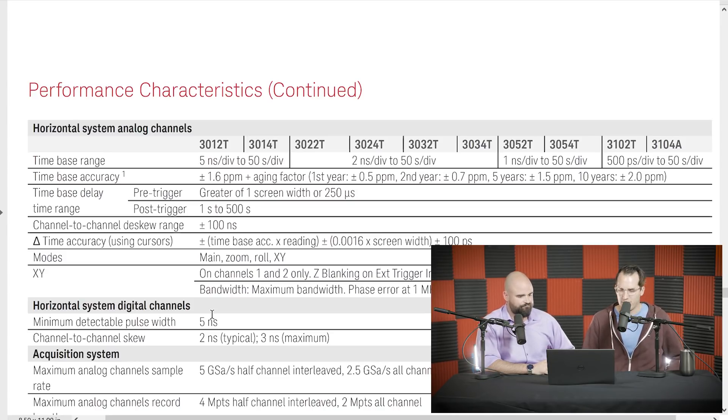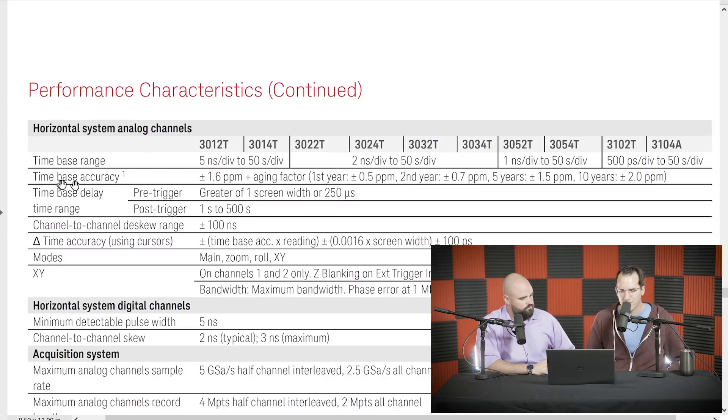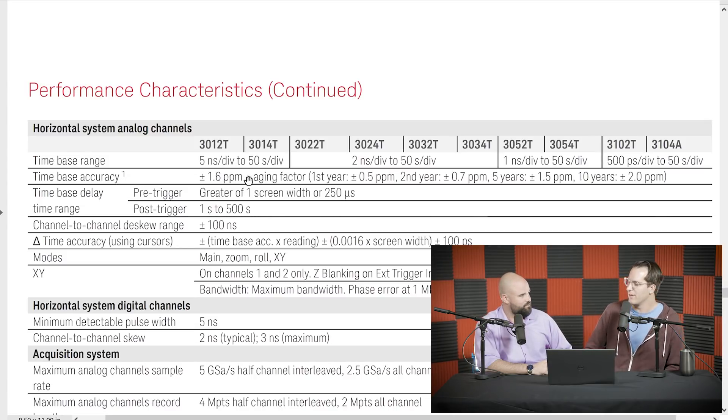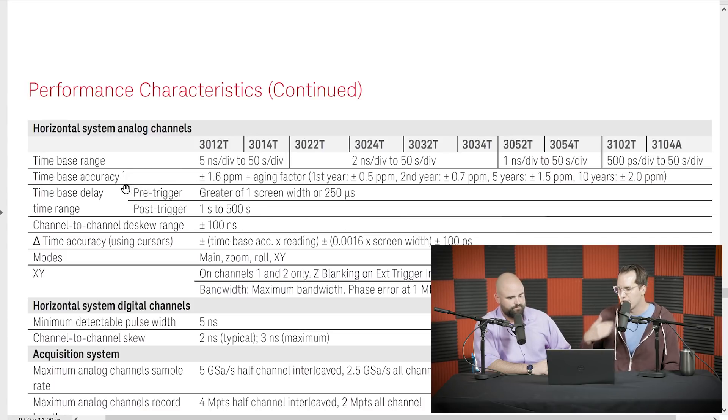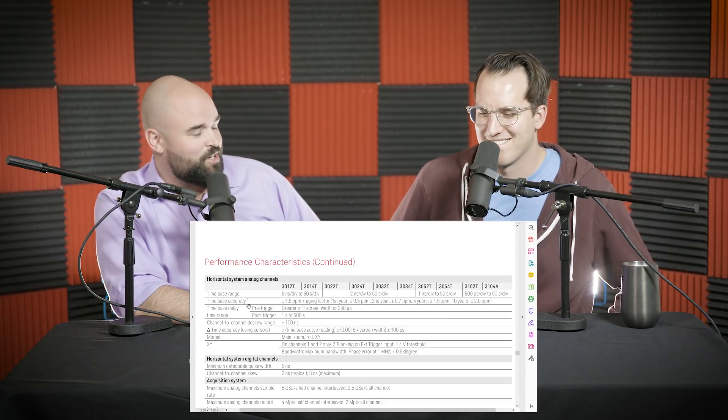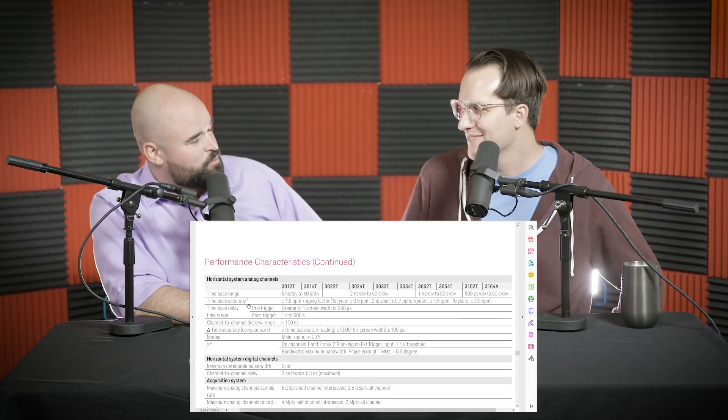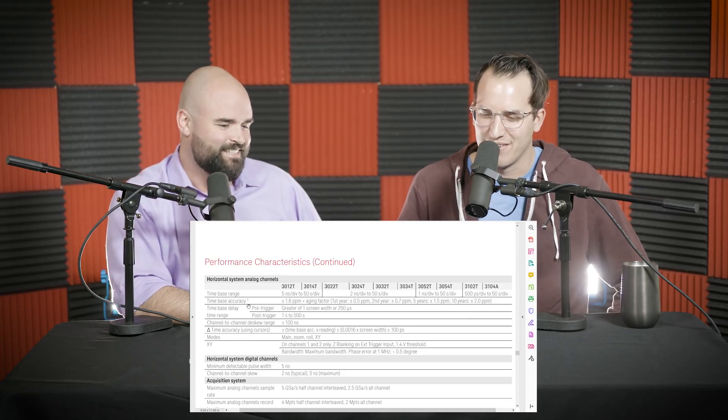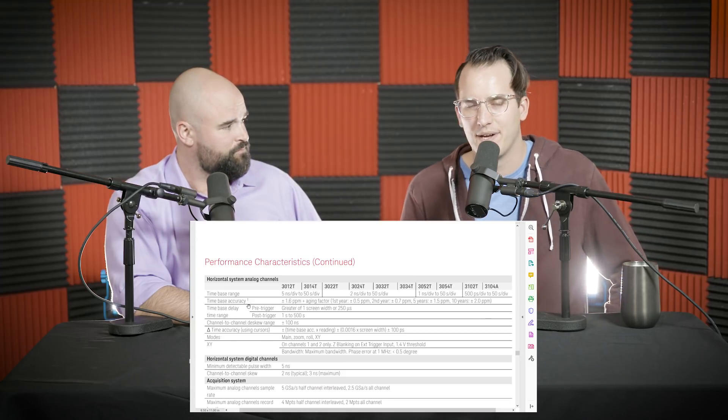Horizontal system analog channels. So this is like your time base accuracy, essentially. Warranted specs. It's going to be in parts per million and then timing chips and hardware, they start to age out. So once you recalibrate, it helps. But things just get old and nasty. Calibration was 30 days ago. Please don't remind me. It's a sore subject. Oh, I'm not there yet. Well, that's because I'm old. I've aged at least five parts per billion. I don't remember the details of PPM versus speccing time specifically. I don't know why we do that. But it's out there. We'll write a blog on it or something.